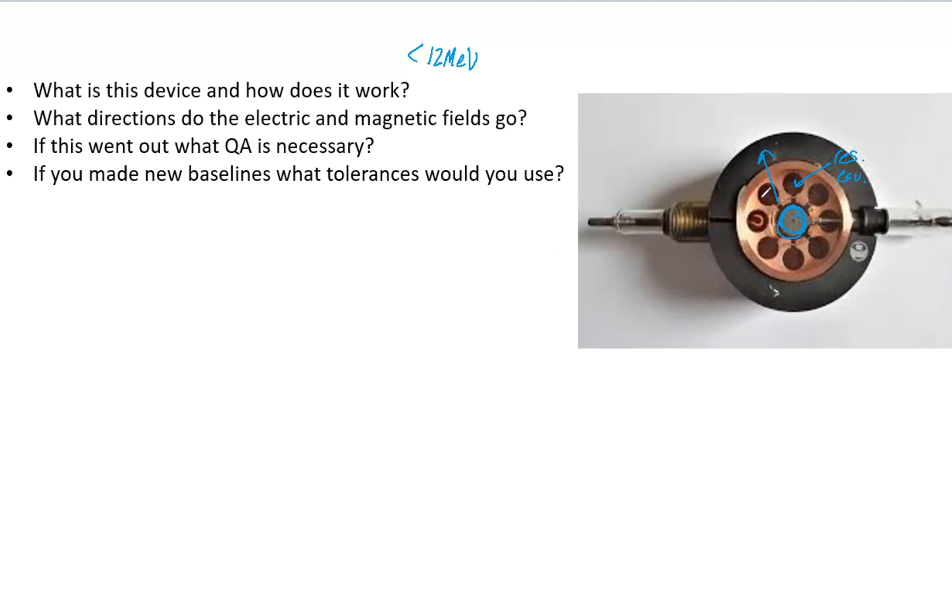So now if this went out, what QA is necessary? You would want to do first outputs—that is absolutely critical. You would also want to check your percent depth doses, and then you'd also want to check all of your beam profiles.